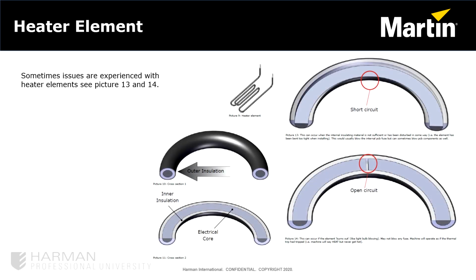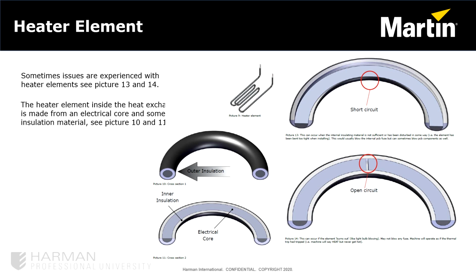Sometimes heater elements have problems. Figures 13 and 14 reference a short circuit and an open circuit respectively. A short circuit is usually caused by a user error. When a faulty heater element has to be replaced and a new part is received, the elements are straight and requires the technician to bend them, then fit them inside the unit. If not correctly done, this process presents a high risk of creating a short circuit. It is suggested to use the ring ends of 2 spanners and push them together to create a smooth curve.